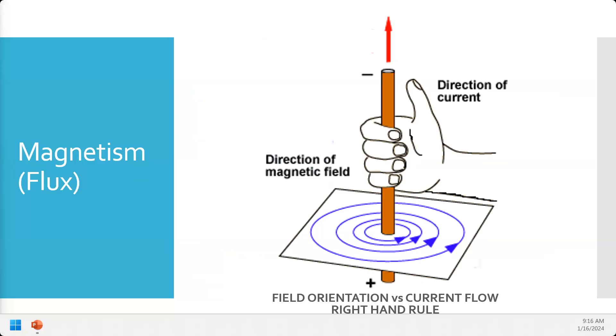In the United States, the power sine wave oscillates 60 times a second, so 60 times a second it flops from one direction to the other. You don't know which way the field is facing when you let go of the button. What's important is: if we ran power through a rod, the magnetic field would be circular around the outside. Conversely, if we run the current through a coil around the outside of the part, the magnetic field would run with the length of the rod.